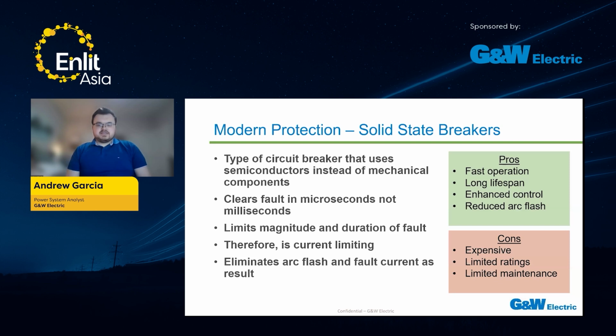The pros for that are fast operation. Once again, microseconds, not milliseconds. They have a long lifespan. There aren't any mechanical parts that need to be serviced anymore. You have enhanced control because, once again, it's electronic. You have a lot more control over things that are electronic and how they respond to different events than you would with something mechanical. And ultimately, it's going to eliminate arc flash risks from your system and make it a lot safer for any nearby workers or people that are in the area.